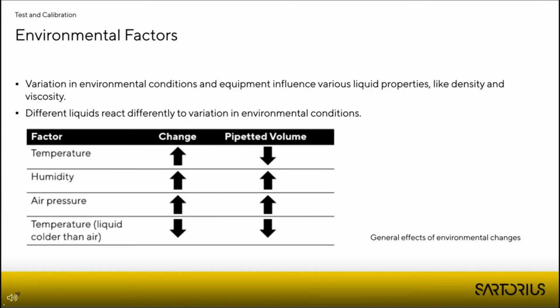Air humidity: when the humidity increases, the airspace is more moist. Thus, less evaporation from the liquid will happen, and as a consequence the dispensed volume goes a little bit up. Looking at the air pressure, increases in the air pressure compress the airspace, and the dispensed volume here will go a little bit up. And last but not least, the liquid temperature: liquids that are colder than the air will cool down the pipettes and the airspace temporarily, and this causes the pipetted volume to go a little bit down.